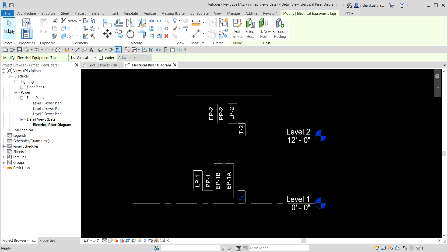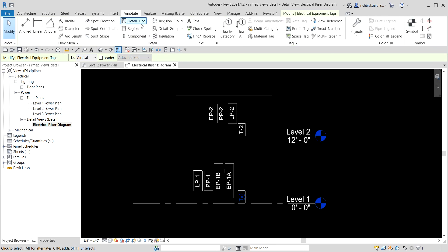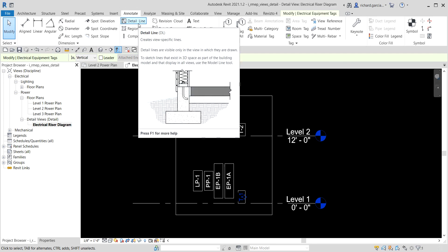Next we'll add detail lines to connect the electrical panels. Since this is just detailing, the lines we create are 2D only - you won't see them in a 3D view. From the Annotate tab, in the Detail panel, select 'Detail Lines'. These are view-specific lines, meaning you can only see them in the view where you created them. If you draw a detail line on a floor plan, it only appears on that floor plan.